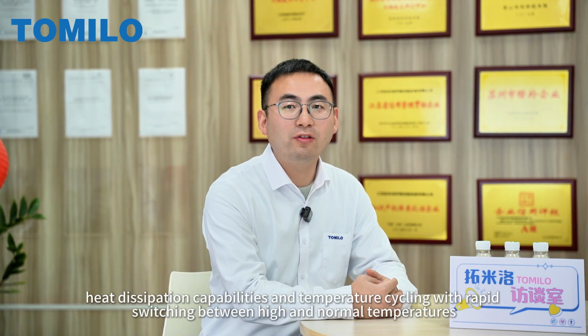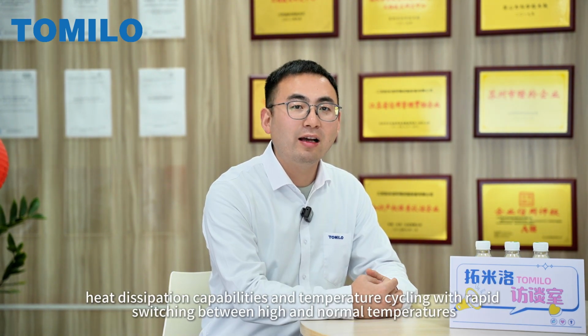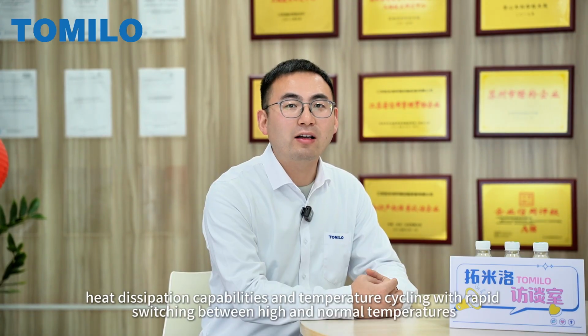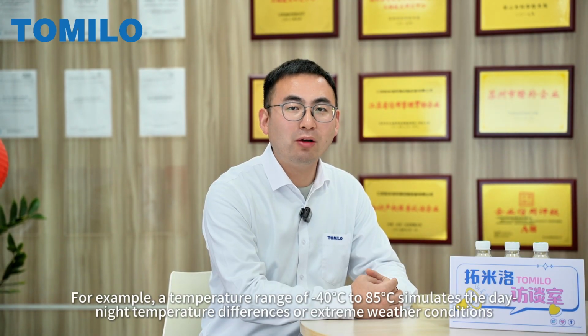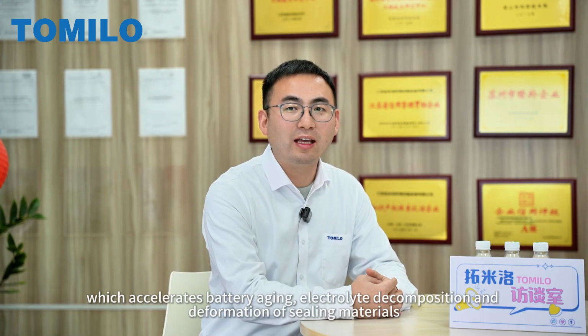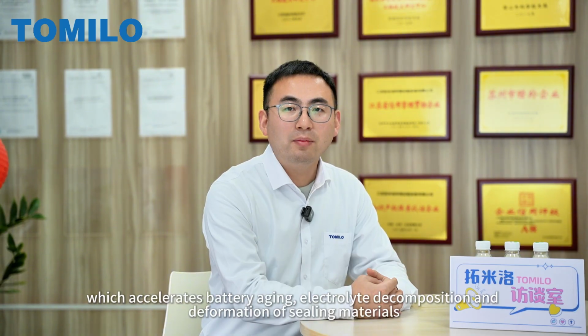This evaluates the performance of energy storage products in high-temperature environments, assessing degradation, thermal runaway risks, heat dissipation capabilities, and temperature cycling with rapid switching between high and normal temperatures. For example, a temperature range of -40 degrees Celsius to 85 degrees Celsius simulates the day-night temperature differences or extreme weather conditions, which accelerates battery aging, electrolyte decomposition, and deformation of sealing materials.